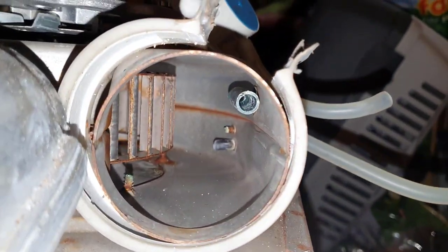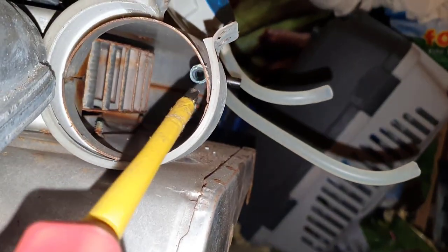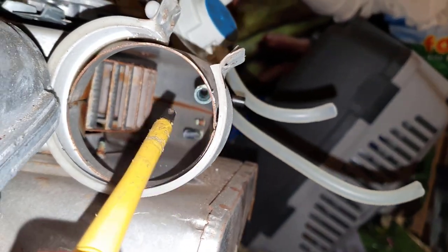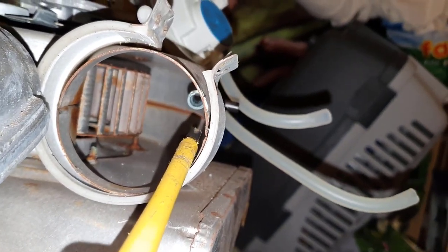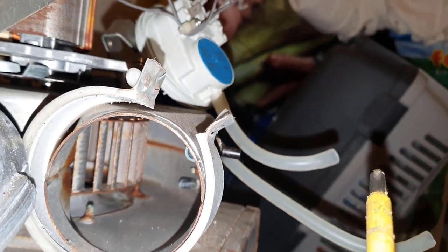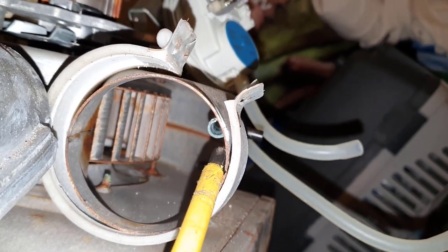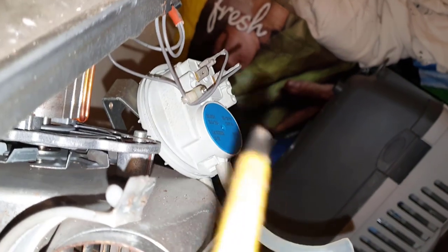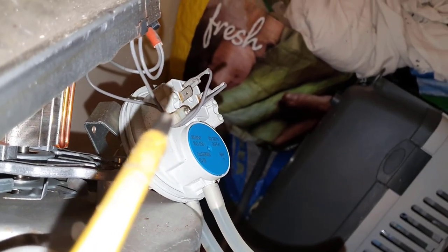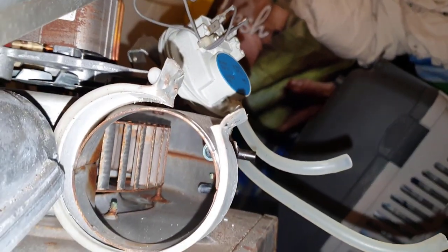That's the fan venturi there. When the fan blows, it causes a differential pressure, and that differential pressure makes the air pressure switch make. If this is clogged up there's no differential, meaning there's no movement of the air pressure switch — the air pressure switch doesn't make, then it won't start the ignition sequence. That's a common fault on one of these boilers.